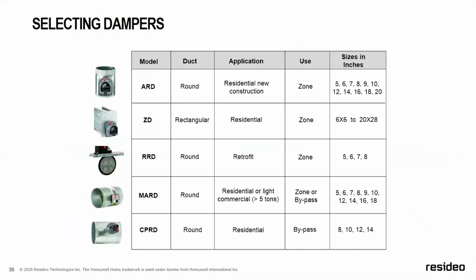Selecting dampers. Here's the different dampers that we offer. Automatic round damper, generally residential new construction. Size ranges are 5 inches to 20 inches. We have the ZD, which is rectangular, 6x6 to 20x28. Always remember, when ordering a ZD damper, the actuator is on the second dimension. This is very important.